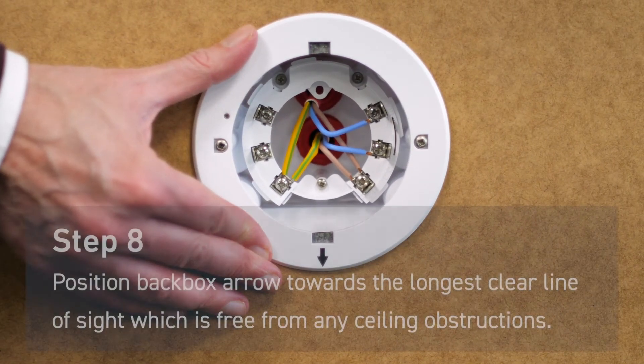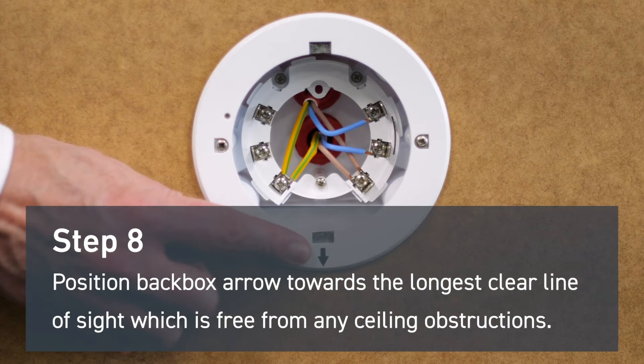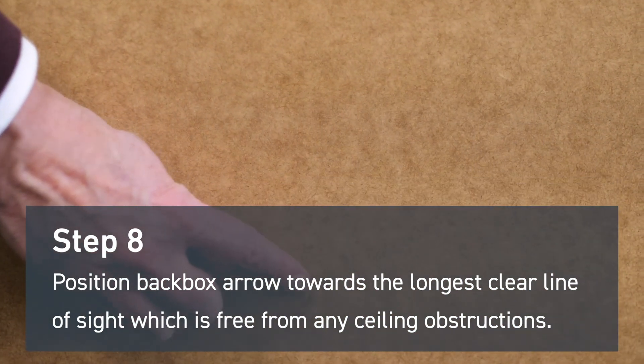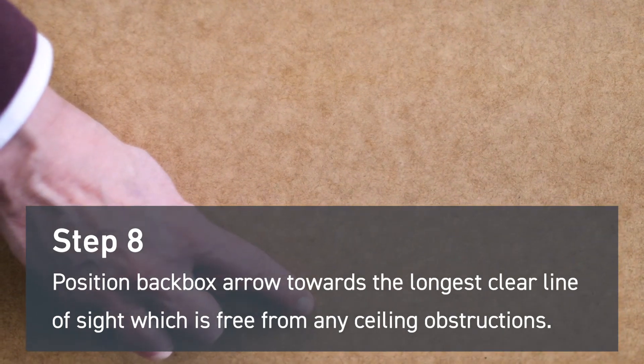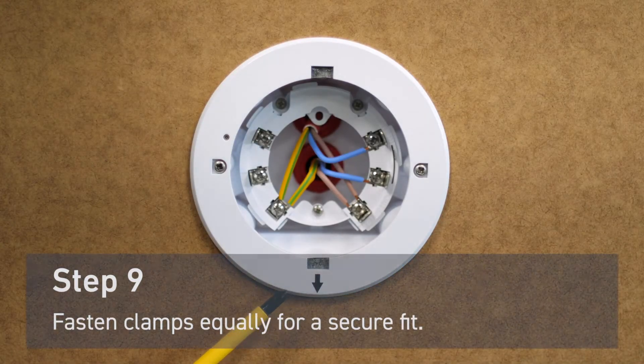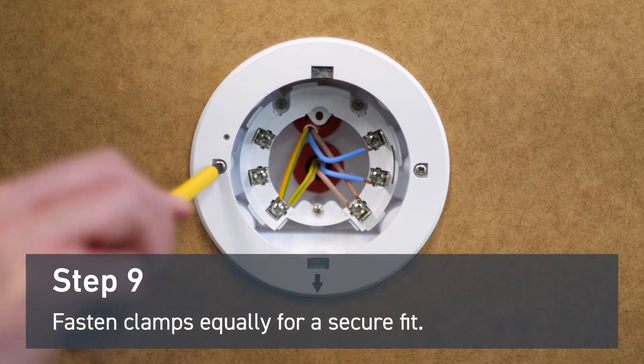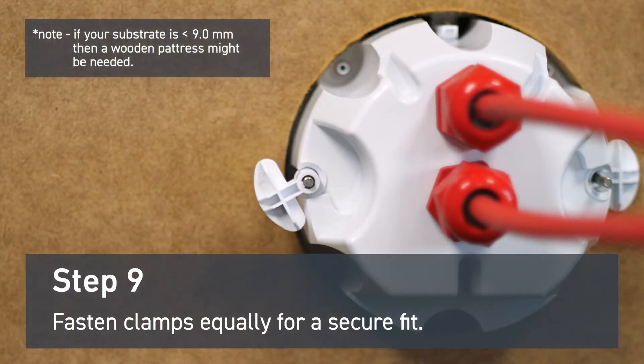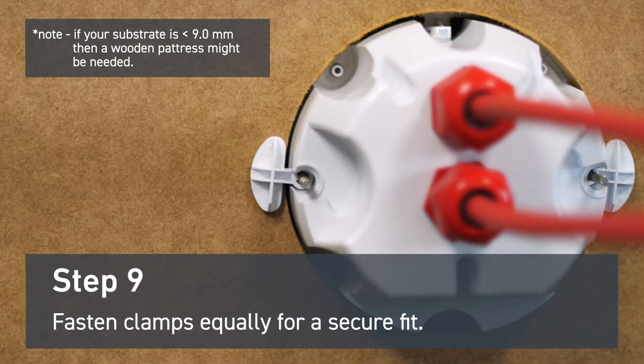Position the back box arrow towards the longest clear line of sight, which is free from any ceiling obstructions. We also advise leaving a 500 millimeter clearance around the device in all directions. Fasten the clamps equally for a secure fit. If your substrate is less than 9 millimeters thick, a wooden patress might be needed to support the clamps.